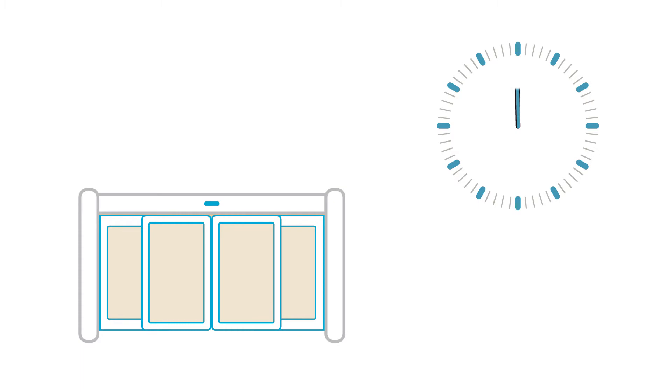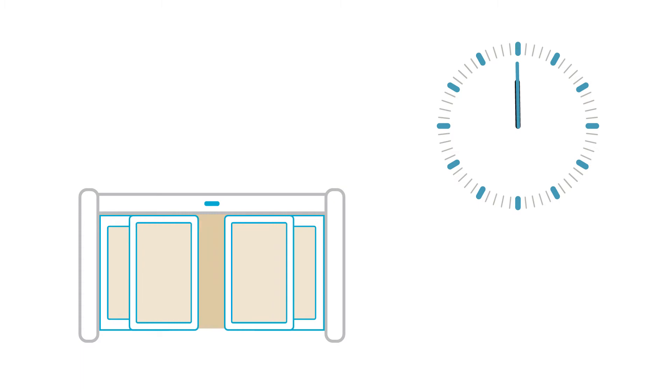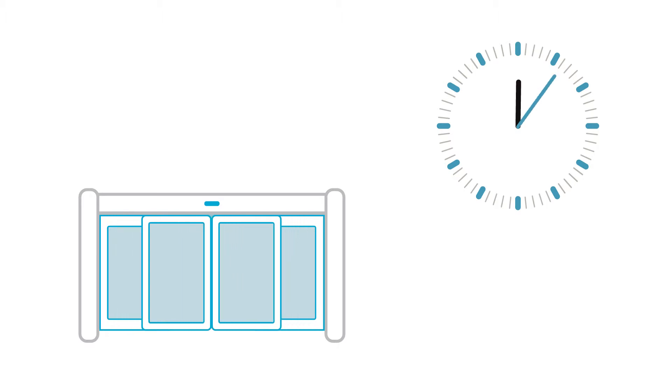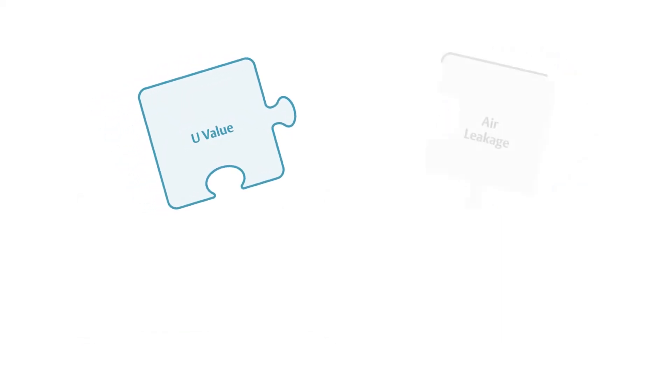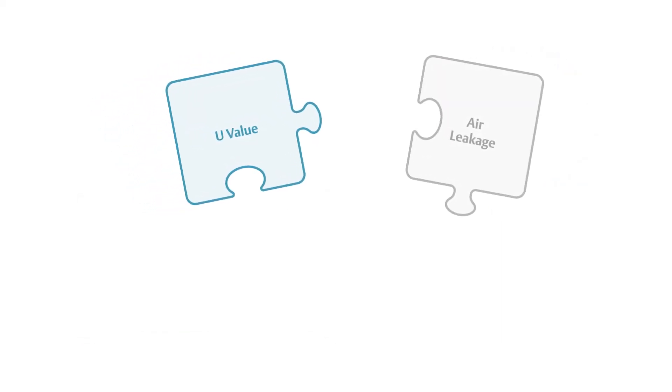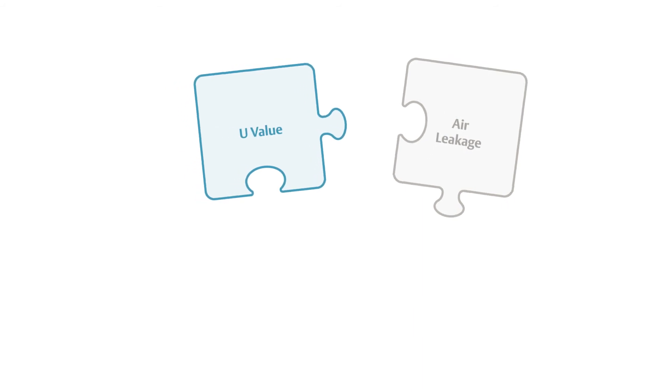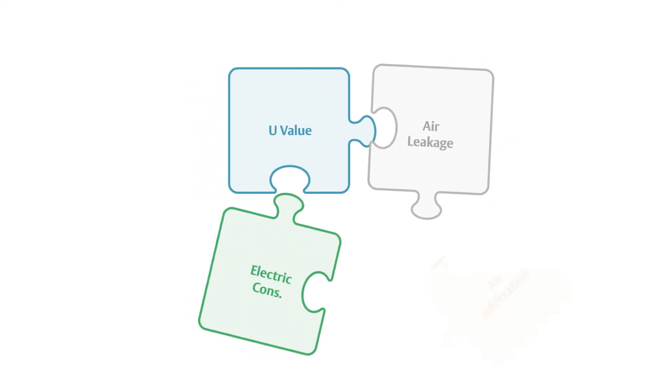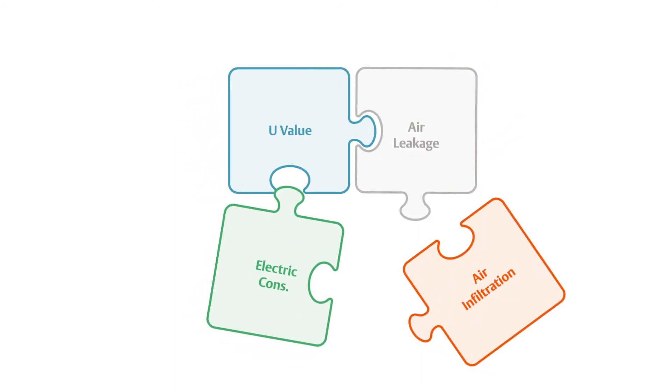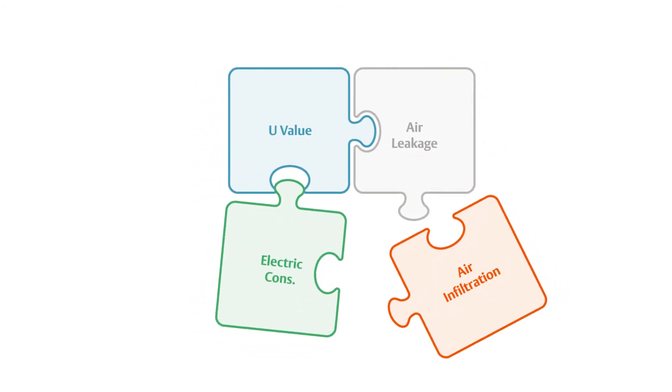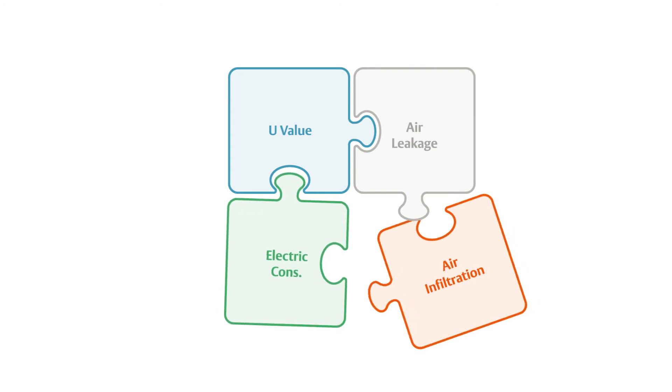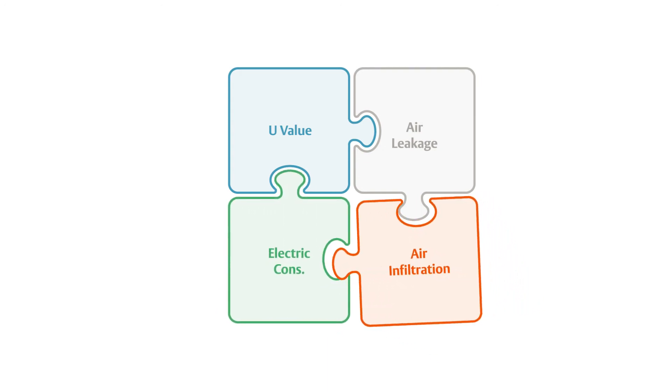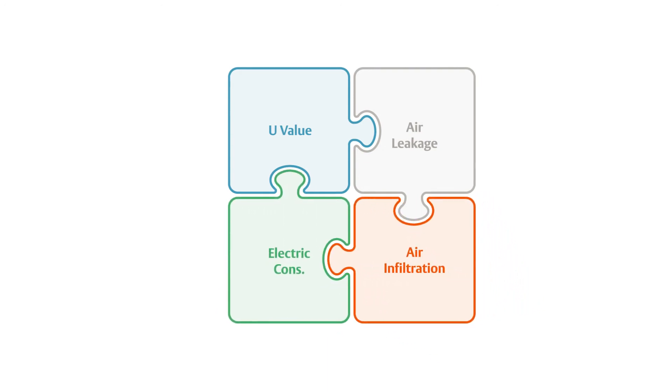Studies show just three open minutes per hour can outweigh a door's U-value. So to know a door's energy impact, we have to consider multiple factors. One is the U-value. Another is air permeability or leakage when the door is closed. The door's electrical consumption is a third. And the biggest is air infiltration during opening and closing.